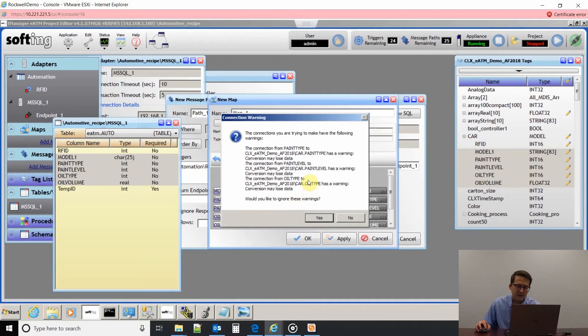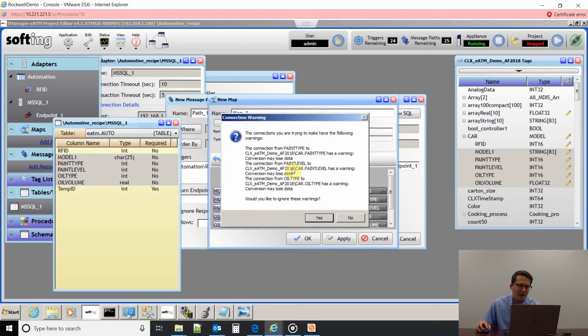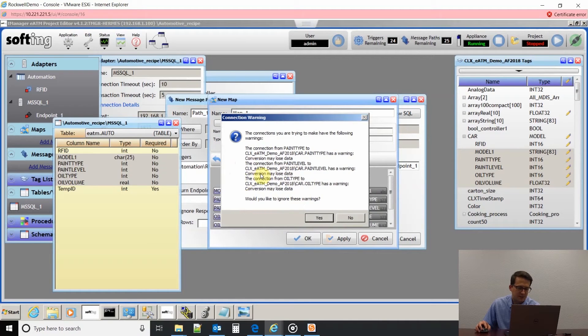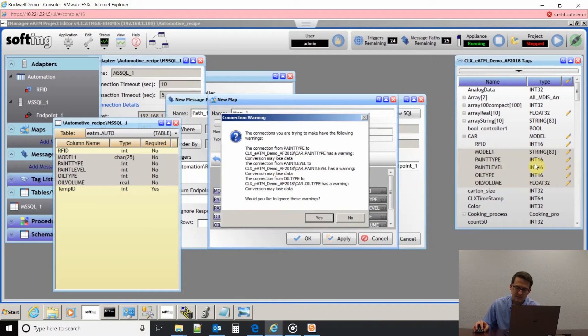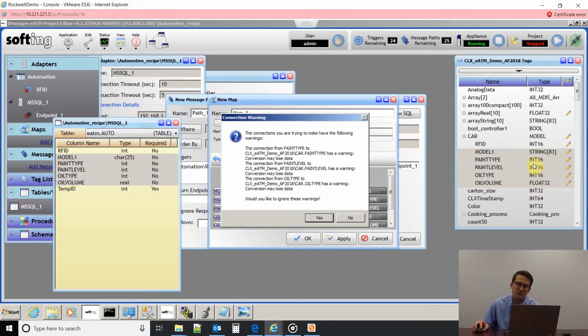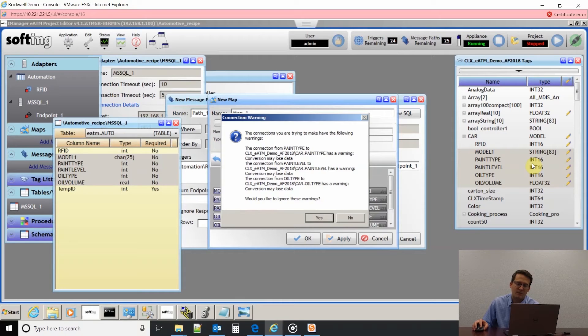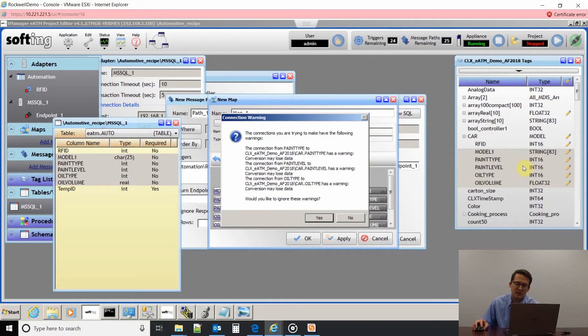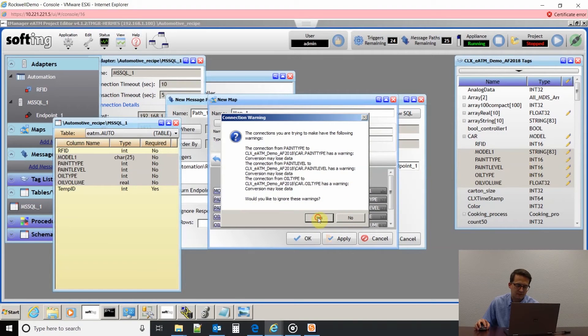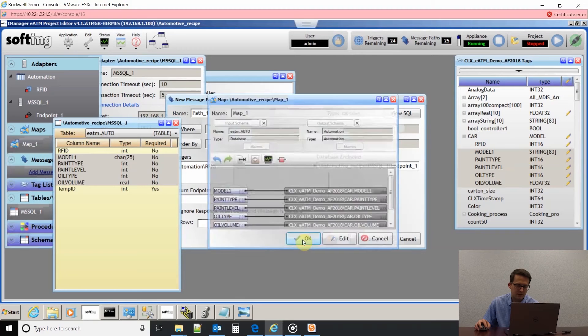Right here, it's giving me a warning because I have a 32-bit integer in my database but it's going into a 16-bit integer in my PLC. tManager will do that, but it's giving you a warning that you could lose data. I know I'm going to be fine with my values that I have set up in my database so that I'm not going to lose any data.